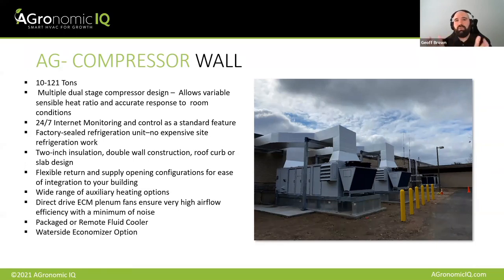And you know, there's a couple of quote unquote weird things about these units that are done for a very good reason. One, they're all water cooled or glycol cooled. We have a packaged configuration available for all of the units, or they can be done as site splits or split fluid cooled units. But we're using a glycol cooler because it allows us to completely isolate the refrigeration circuits, those small pods that I talked about, from what's happening outside. And so it means that, in particular with low ambient conditions, so when it's cold outside, we're able to still do full cooling and dehumidification without having the compressor circuit need to work in a -20 or -30 or -40 degree environment.